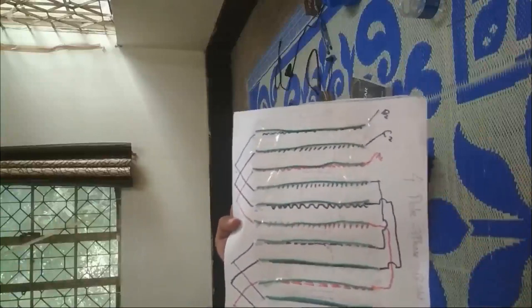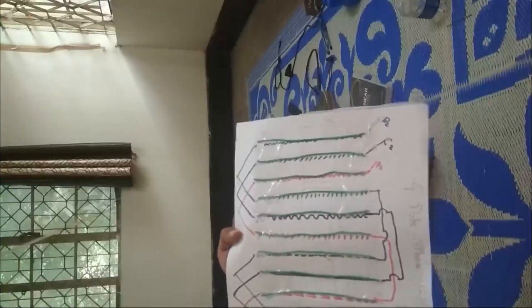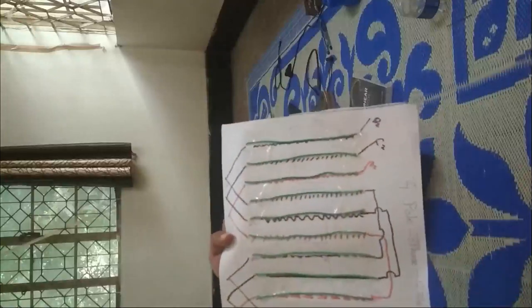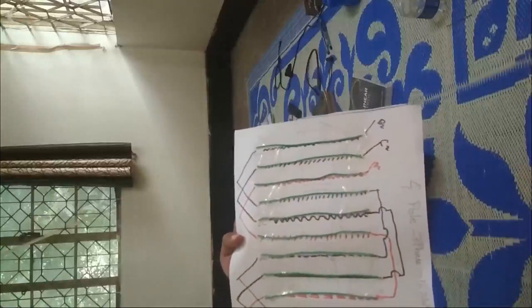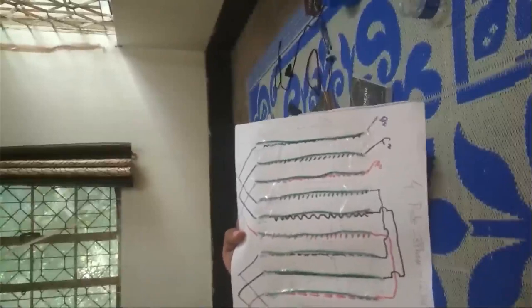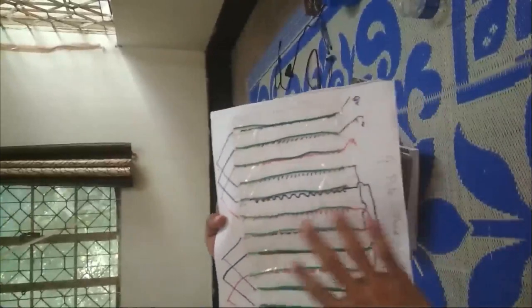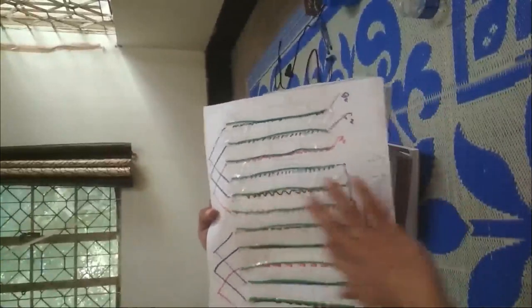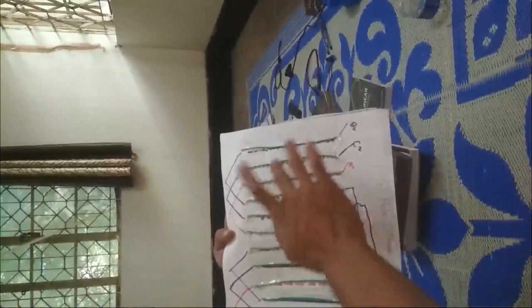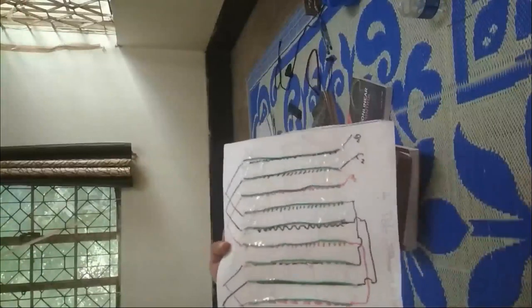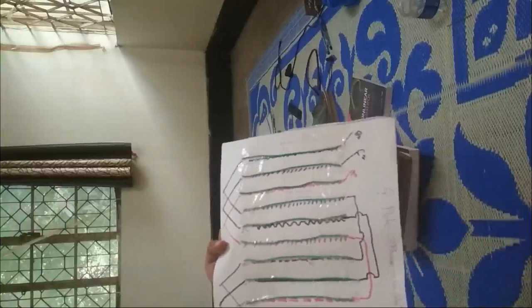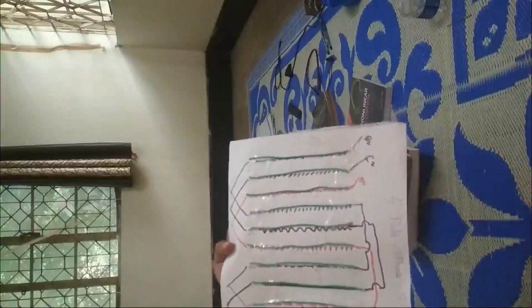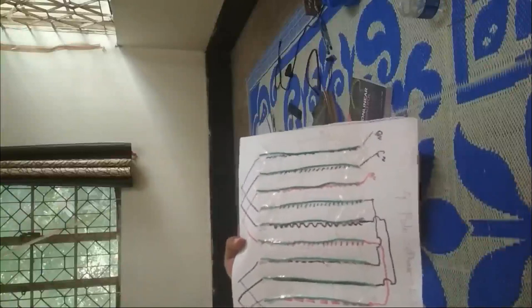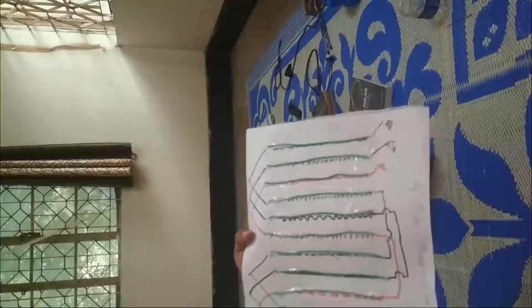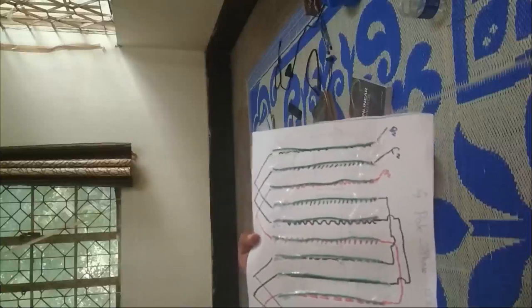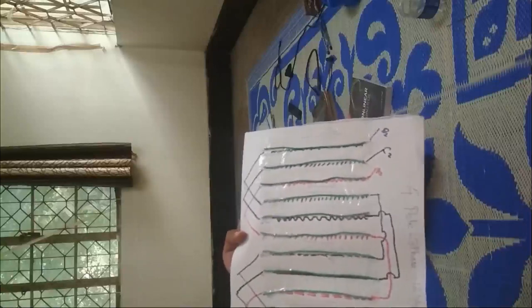Now after that, what should be the next position? Because for 12 slots you have 4 conductors per phase, and you have placed only 3 for C. One is at 5, another one is at 8, another one is at 11. So what should be the fourth one? It must be at 11 plus 3, that is 14. But 14 minus 12, how much will that give you? That will give you 2.